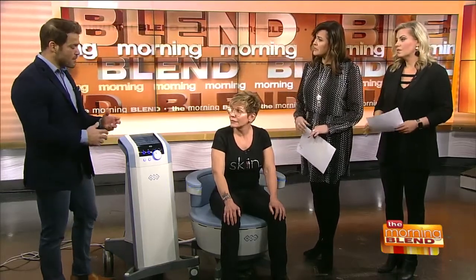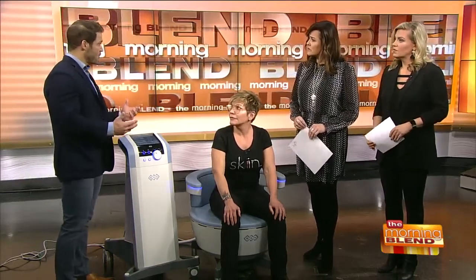Okay. Are there some people who wouldn't be a good candidate for this? Yeah, so we don't want to treat anyone who's currently pregnant. It's magnetic, so if it reacts with metal, that metal will heat up on them. So we want to make sure that we're not treating anyone who has metal implanted inside of their body. That includes a copper IUD. That includes piercings of any sort, clips from a previous surgery. So those are the two things, pregnancy and metal, that we really want to stay away from.